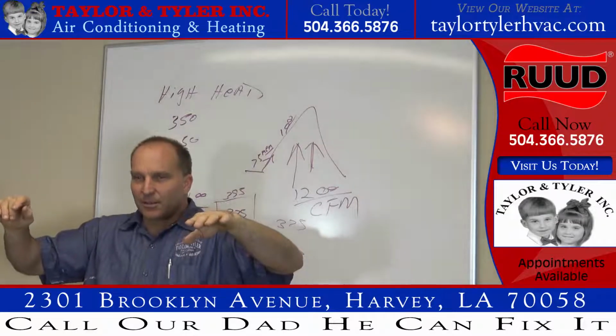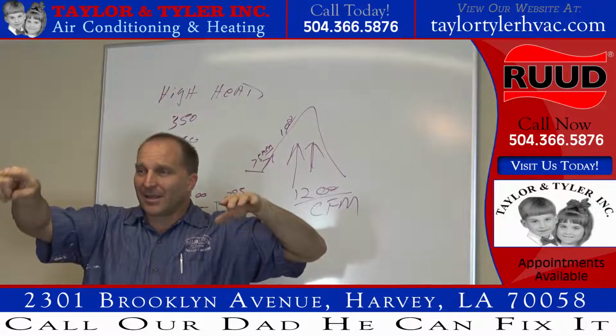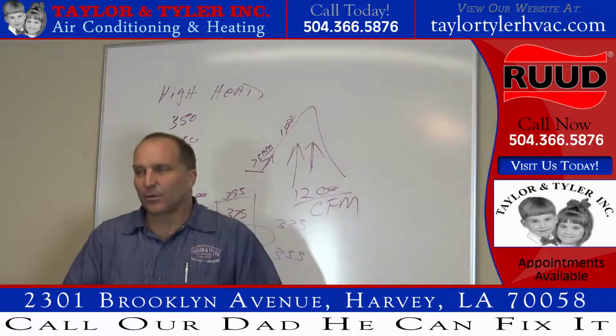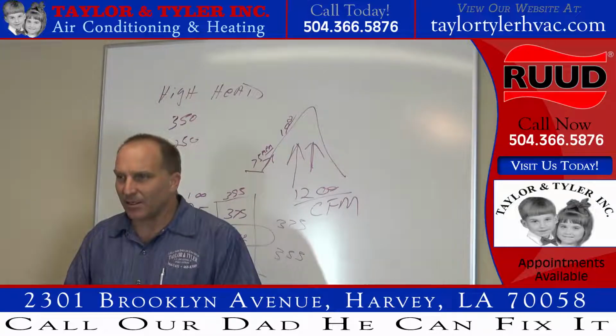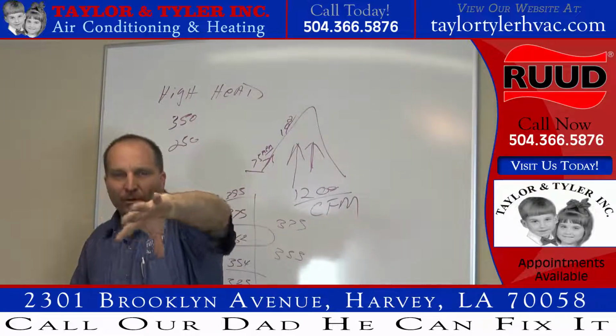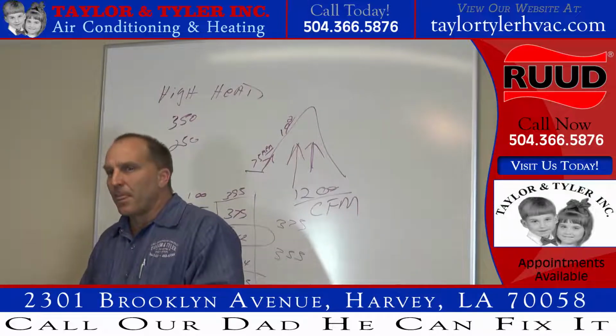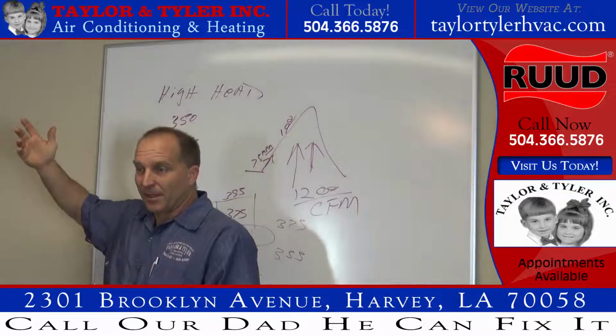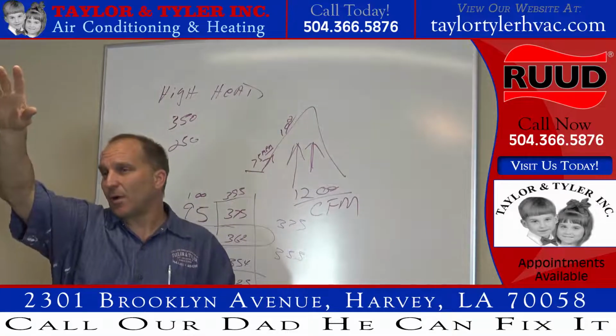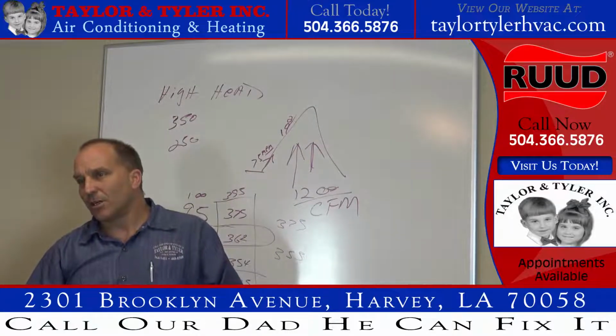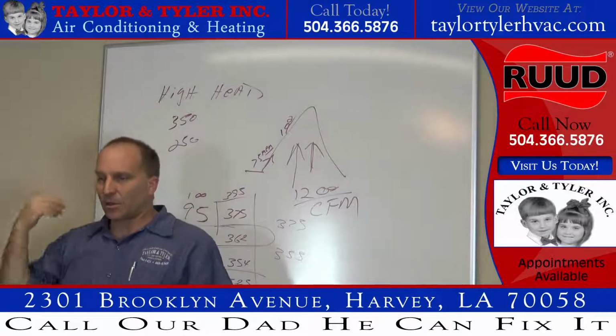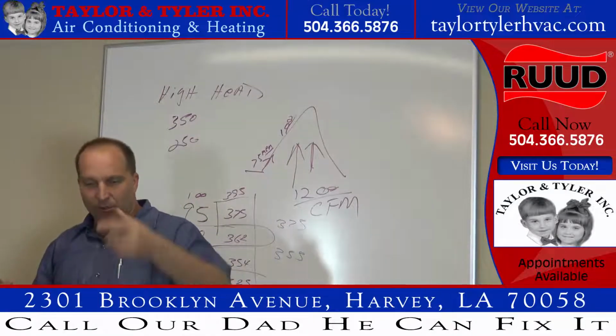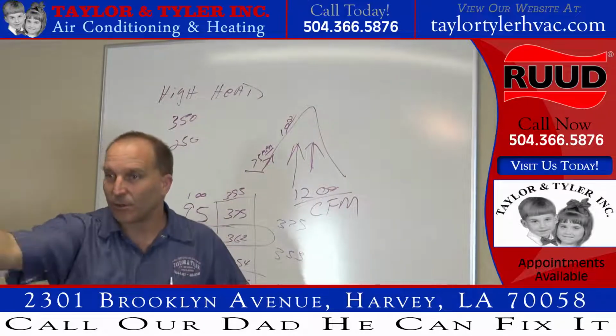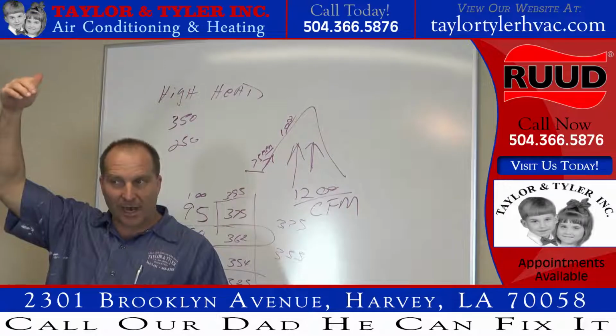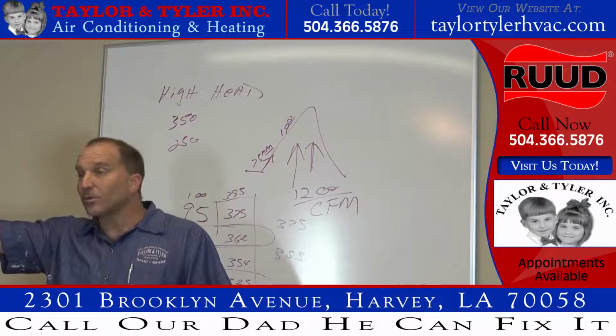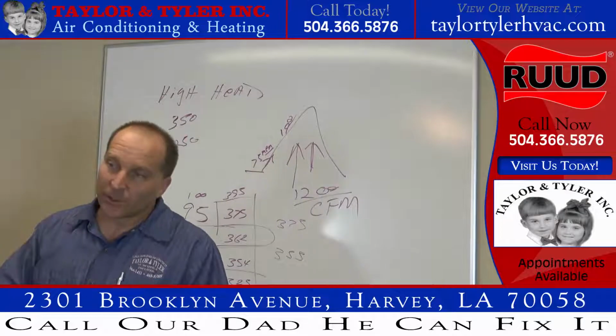Okay? My system is off right now, so my pressures are equal. As soon as you turn that system on, that refrigerant tries to get out of the system, and it can't get out. You've got your gauge sitting there on the port, right? You're reading the pressure on that gauge. So all of a sudden that refrigerant is sucking through the suction line, compressing through the compressor, building up in the condenser, right? Trying to get through the dryer, and some's getting through, but not all of it. So it's going to send your head pressure skyrocketing, right? You're going to watch your head pressure and your suction pressure, and your suction pressure is going to come down because the refrigerant's not getting through the dryer, and your head pressure is going to skyrocket, right? It's almost like you're pumping it down. But you're getting some refrigerant through there.